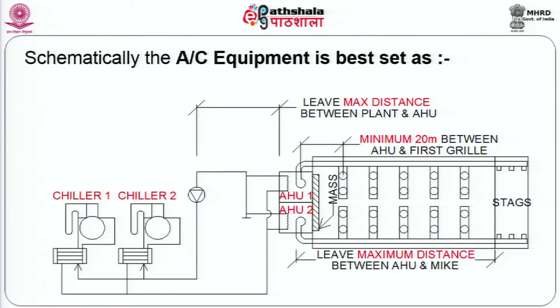I will come back to the first slide, which I set out to highlight the points that I had made. You will now see on the screen the use of mass and distance in the parameters that are desired. The noisiest equipment, basically the chillers, are expected to be as far away as possible. This is what is meant here. Leave the maximum distance between the plant and the air handling unit room, because the link between these two is purely by piping, and piping very rarely suffers a larger amount of thermal loss.